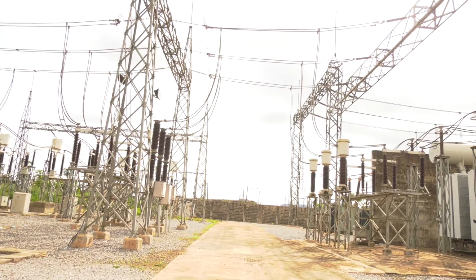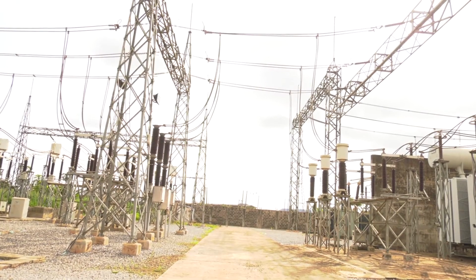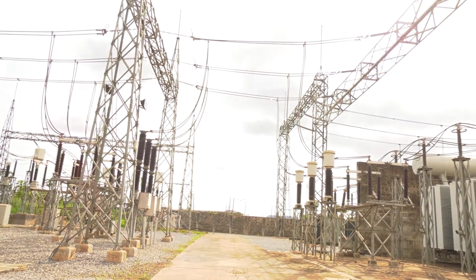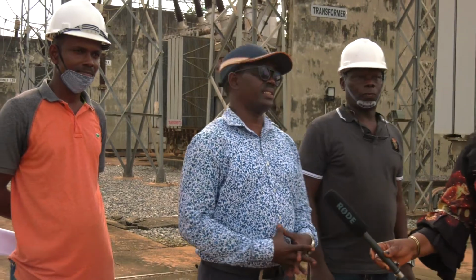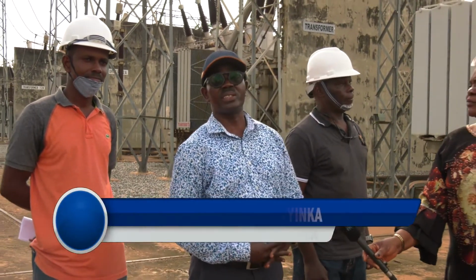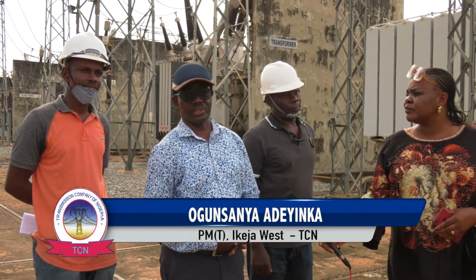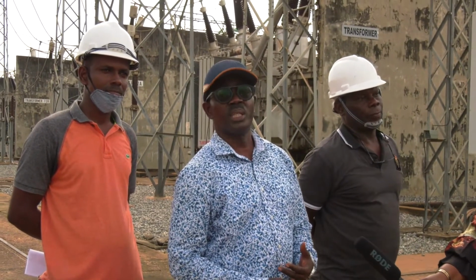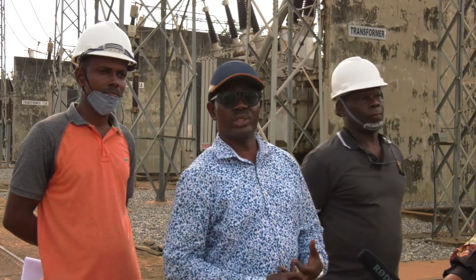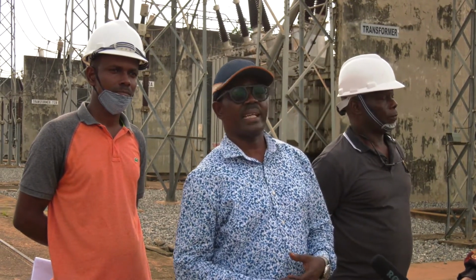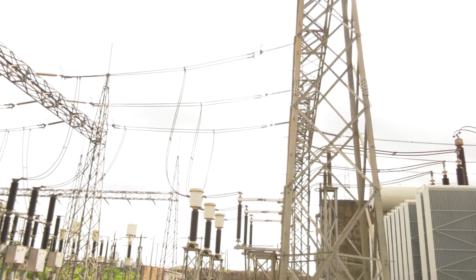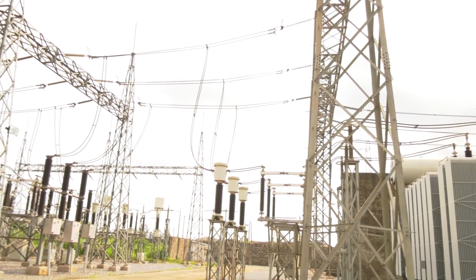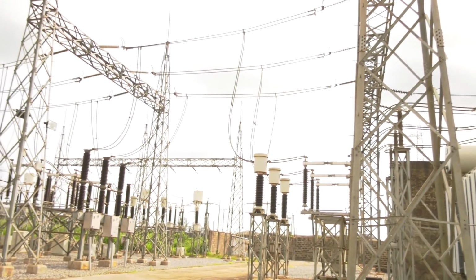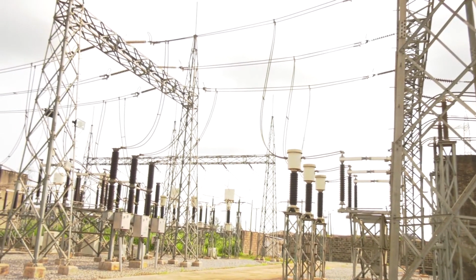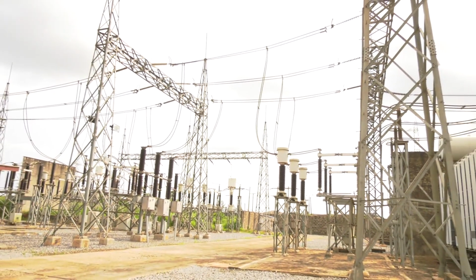At the switchyard of the transmission station, Engineer Ogunsonya explained the components of the station. Ikeja West is a 330/132 substation, and our 330 lines are coming from thermal and hydro generation through Oshogbo. Ikeja West was commissioned in 1977 with 4x150 MVA transformers, making 600 MVA capacity.